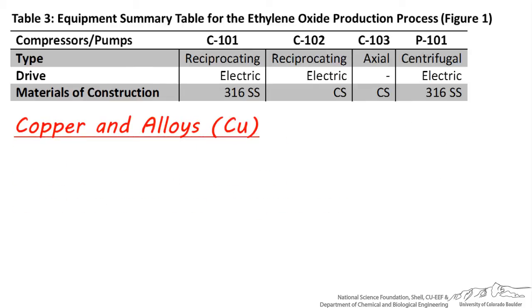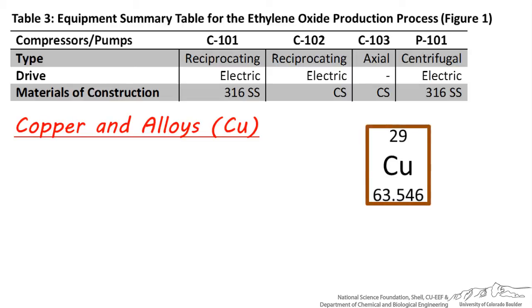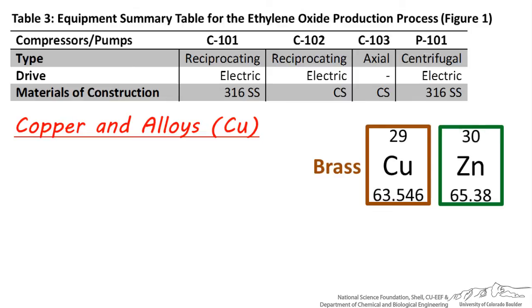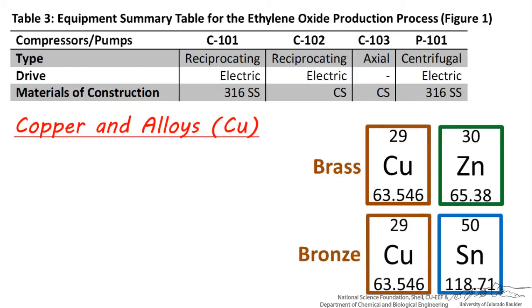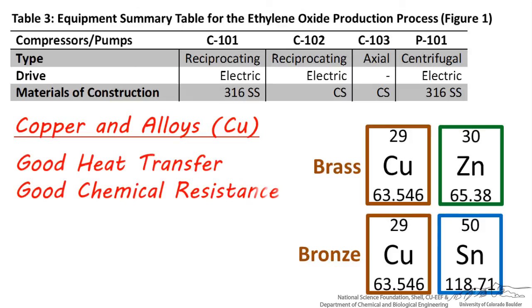Copper, abbreviated CU, and its alloys — which include brass and bronze — are mostly made of copper. Brass is an alloy of copper and zinc, while bronze is copper and usually tin, though other metals and nonmetals can also be used. Copper alloys are a good material to use for heat transfer and for most chemicals, except oxidizing acids like sulfuric or nitric acid.